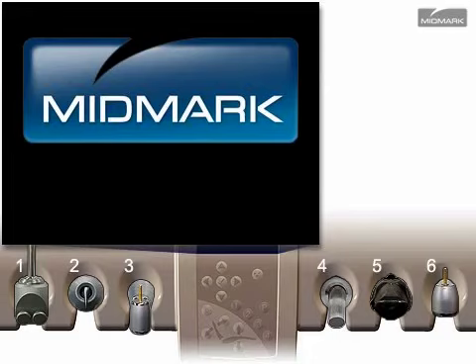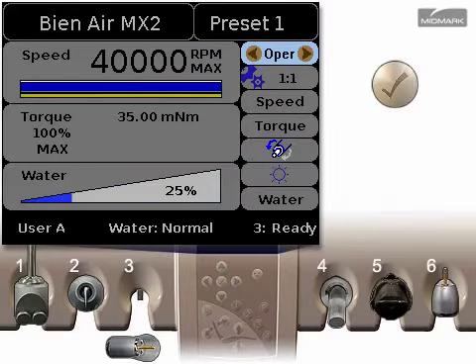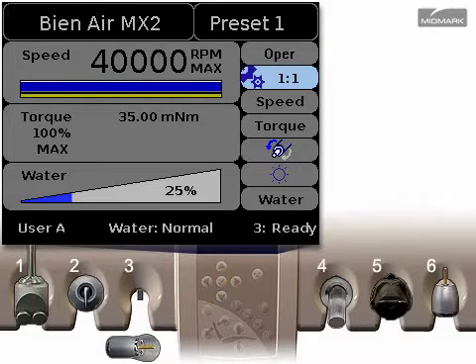Bien Air Handpieces Gear Ratio Sets. To change the set of gear ratios available to a specific user of a Bien Air electric handpiece, begin by pulling the handpiece from its holder. Press the check button to enter edit mode. Use the up or down arrow to highlight the gear ratio setting.